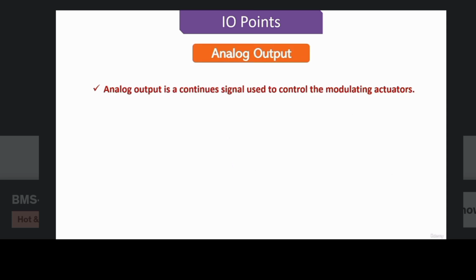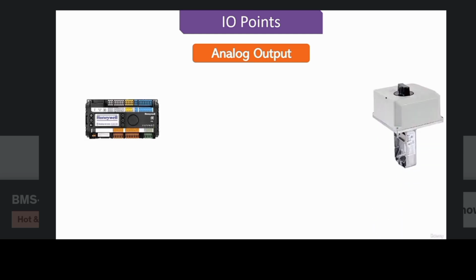Analog output is a continuous signal which is used to control the modulating actuators. A 0 to 10 volt DC signal used to control a modulating valve actuator is an example of analog output. Here is an example where the DDC controller uses a 0 to 10 volt DC analog output signal to control the opening and closing position of a valve actuator. If we want to fully open this valve actuator, the DDC will send a 10 volt DC signal, and if it wants it to open partially, like 70%, then a 7 volt DC signal will be sent to this valve actuator. And in response to this signal, the valve actuator will open or close. So in this way, we can control the valve actuator to open or close to different positions using an analog output.